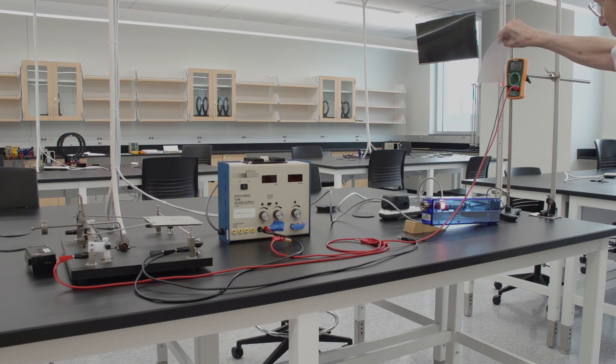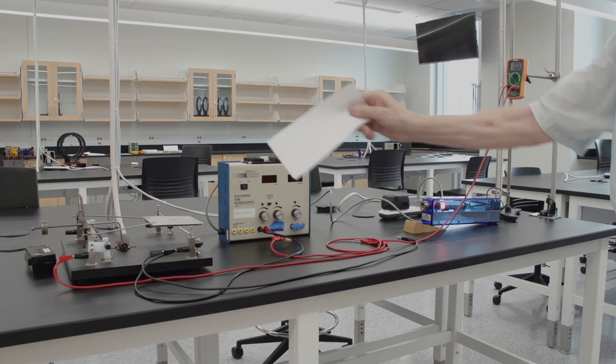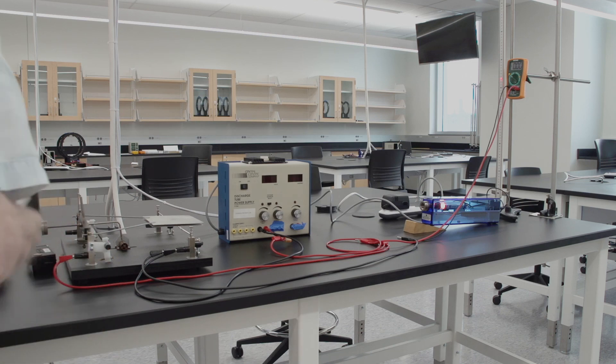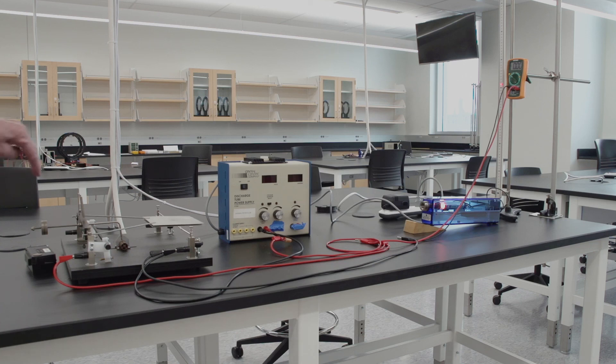We're going to measure where that spot is, which measures the tip of that mirror with a lot of accuracy because of the lever arm. So I can just demonstrate that by just tapping this just a little bit, and you'll see that move up and down because it tips this mirror back and forth.